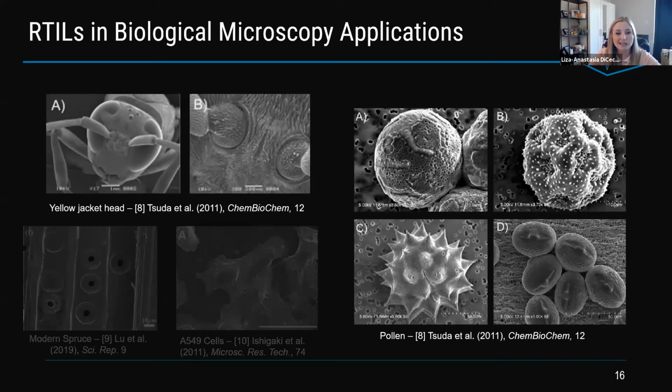A key part here is the morphologies of these samples. They have really sharp features, and especially with these star-shaped structures, they found it's usually really hard to mitigate charging and those bright edge effects at sharp features. In their research, using ionic liquids helped mitigate those edge effects. They're not completely gone, but in comparison to conventional methods, it did help a little bit with these sharp features.